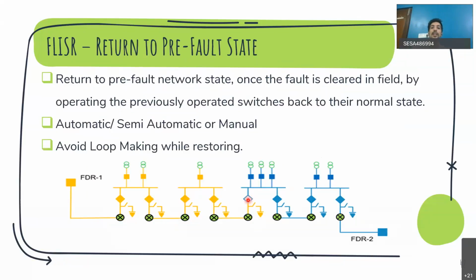So this way you can easily identify when a fault has occurred, where it has occurred, isolate it, restore the non-faulty section, and once the fault is cleared, bring it back to the pre-fault state within a few clicks. That is why this is very important and probably the most sought-after DMS application.